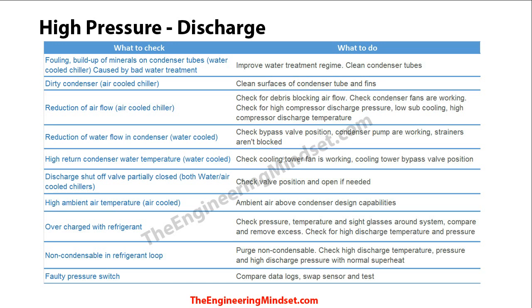It could also be that the discharge shutoff valve is partially closed — uncommon, but worth checking. With air-cooled chillers, it's possible the ambient air temperature is above the condenser's capabilities, meaning it simply can't operate in those conditions. You may need to wait for it to cool down or adjust the chiller's parameters and set points, but check with the manufacturer first.